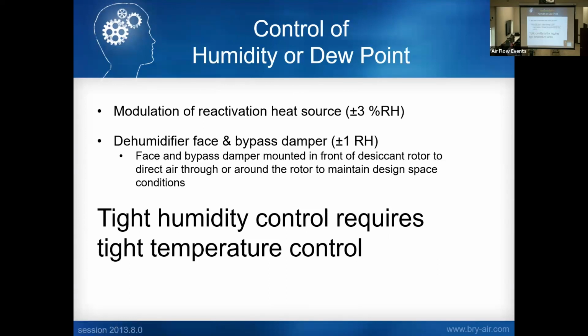Now we start talking control of humidity. Basically, modulating the reactivation heat source is typically how we would do it. You get plus or minus about 3% RH if we do that. If you want tight control, we do face and bypass around the desiccant rotor. We don't really modulate the speed of the desiccant rotor for humidity control. So we either modulate the reactivation heat source or the face and bypass dampers around the desiccant rotor. Again, tight humidity requires tight temperature control. I've been on jobs where someone else was doing the temperature control and we were doing RH control, and if the temperature is fluctuating, it becomes a back and forth over whose units are not performing.